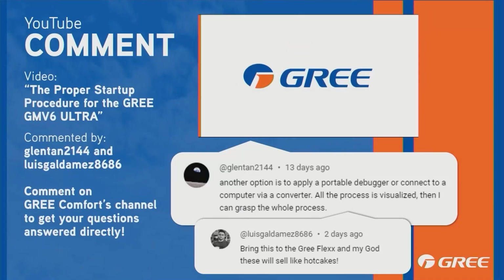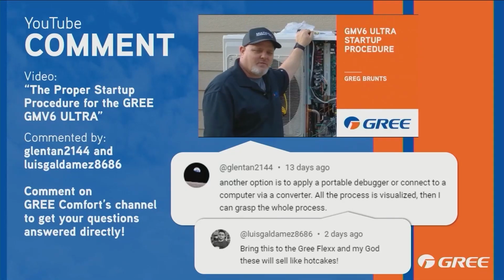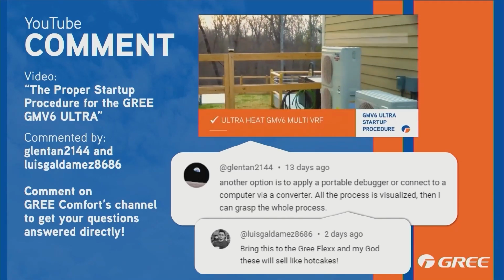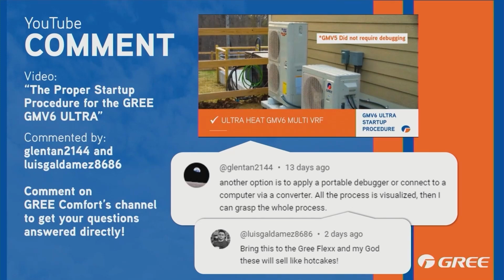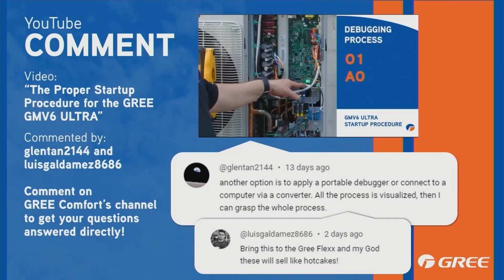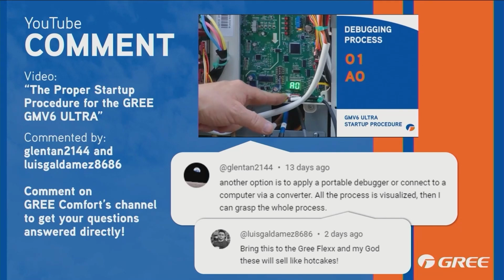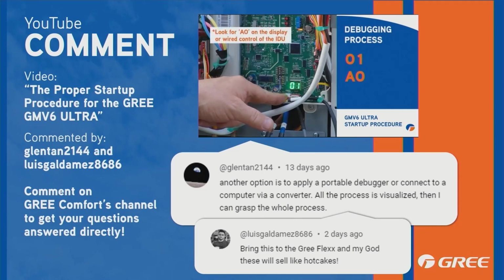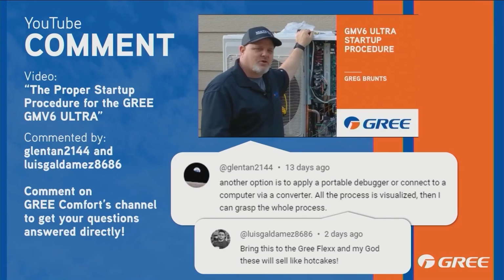Let's talk about the comment. Another option is to apply a portable debugger or connect to a computer via converter. All the process is visualized, then I can grasp the whole process. That's definitely something that you can do. We do have a portable commissioning tool that can connect to this, and it assists in the startup process. It is not required to use that tool for that startup process. It's a simple push button process, but either way, you can do that. The portable debugger also shows you your temperatures and your pressures for everything on the system.